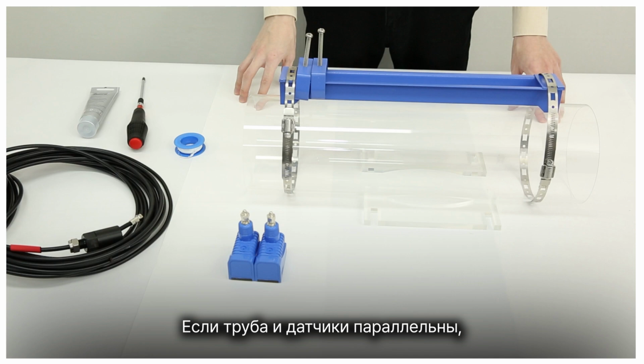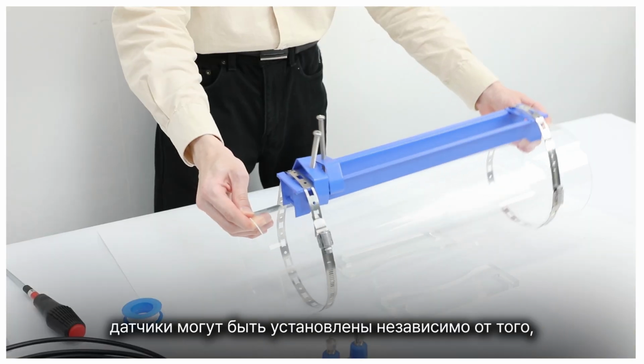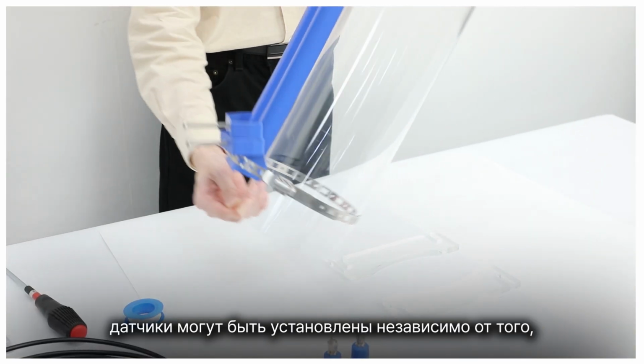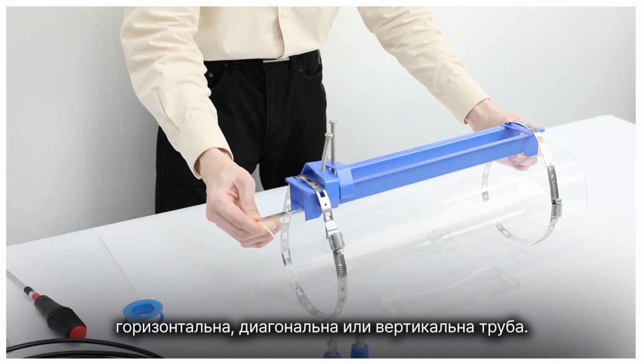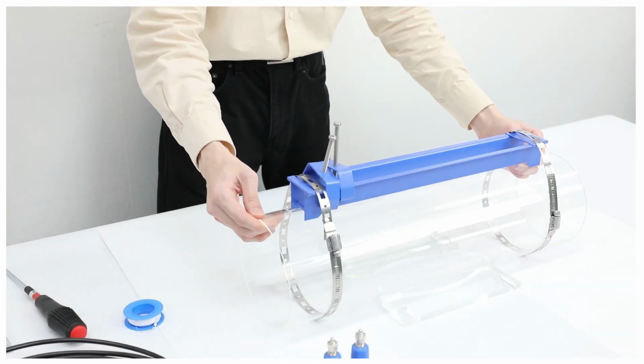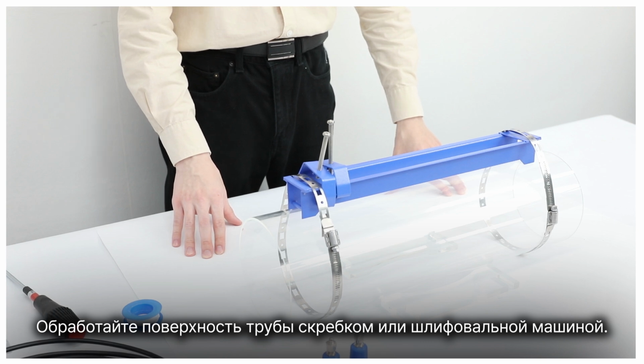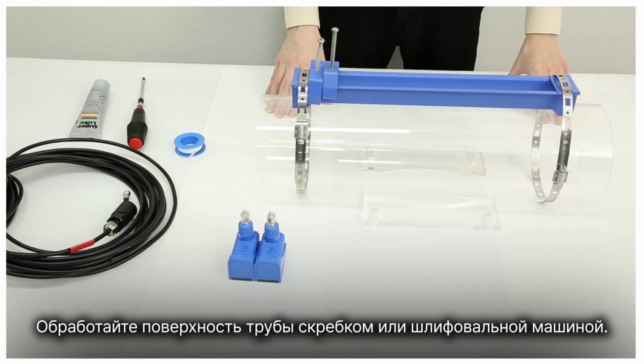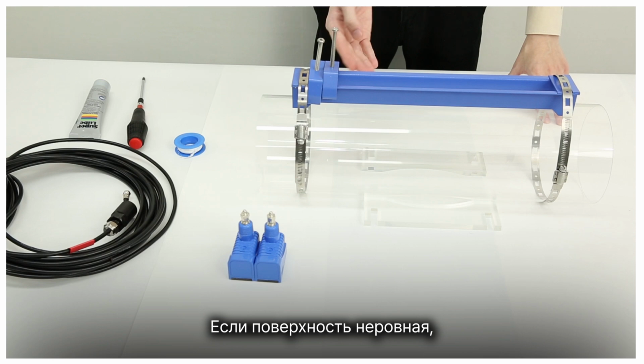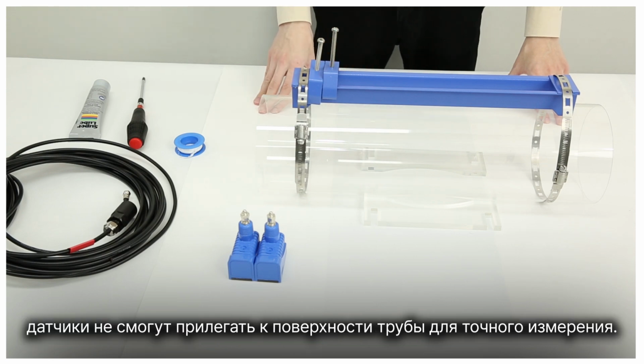As long as the pipe and transducers are parallel, the transducers can be installed regardless of whether the pipe is horizontal, diagonal, or vertical. Smooth the pipe surface by using a scraper or a grinder. If the surface is uneven, the transducers cannot adhere to the pipe surface for an accurate measurement.